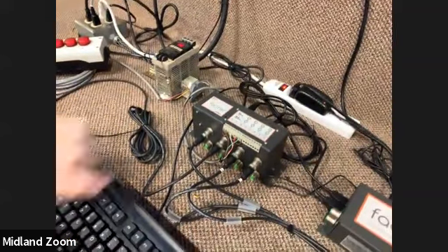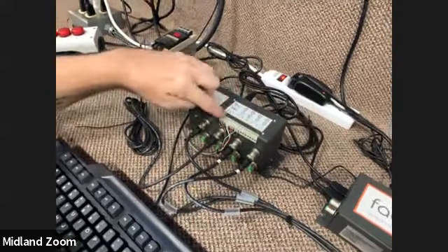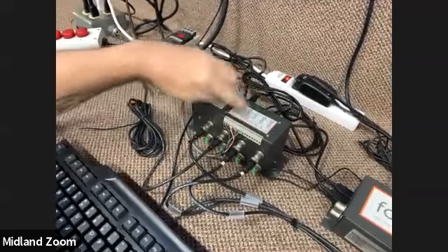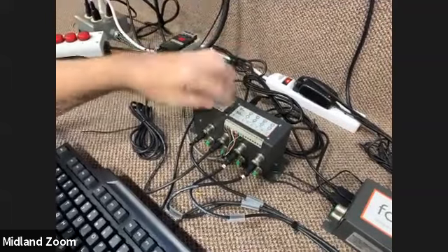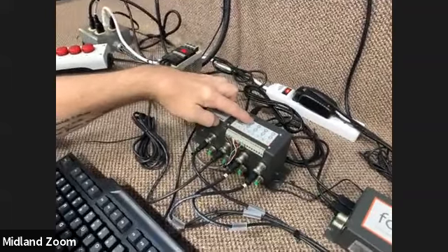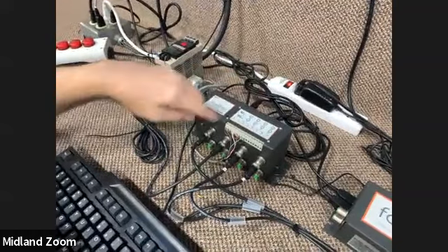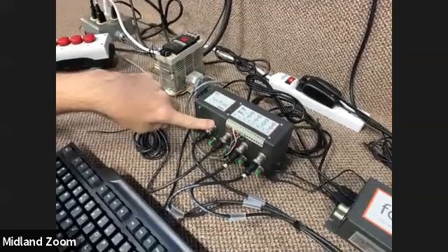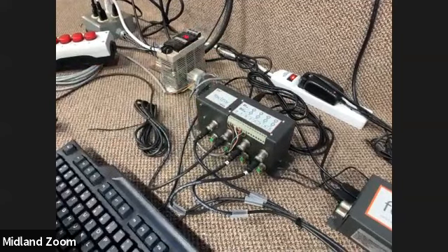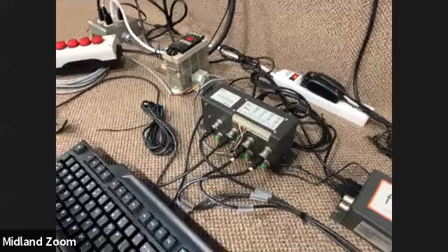And the input numbers are here based upon where they're wired in? Yep, exactly. So you have your inputs here, which coincide with the markings there. And the one thing that a lot of people mess up is outputs start with 0, not 1. So you have 0 through 7. A lot of people will connect to here thinking it's 1, so there's a lot of simple troubleshooting that goes on there.